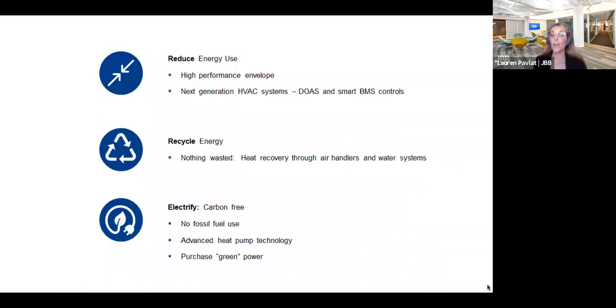For reduce, as Nate touched on, we have a high performance envelope. The insulation on the facade was upgraded for a better thermal barrier, and we're reducing fan energy by going to DOAS, which I'll explain on the coming slides. For recycle, nothing is wasted. We're using condenser water heat recovery, essentially capturing every last BTU before it leaves the building. And electrify refers to our plans to implement air source heat pumps in the future.